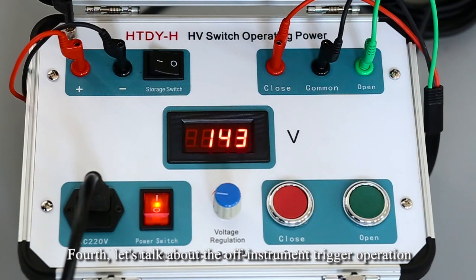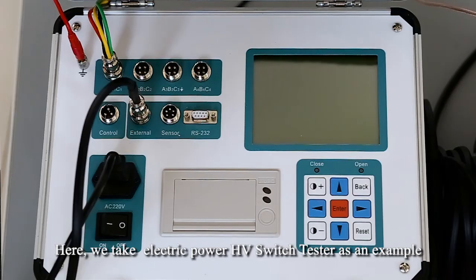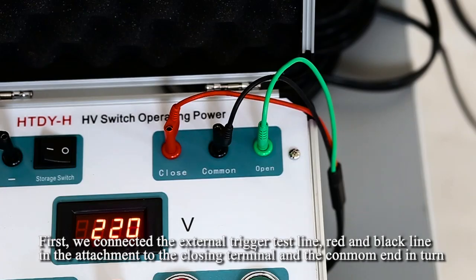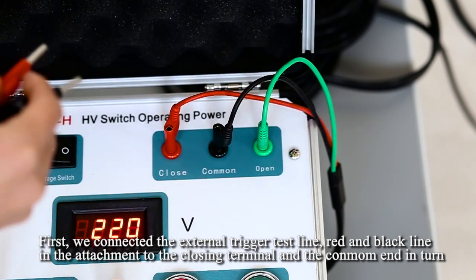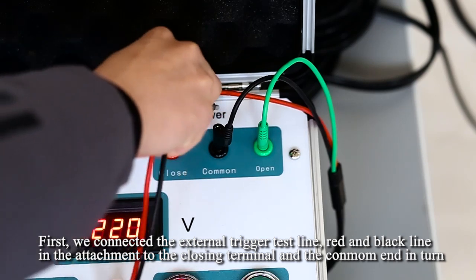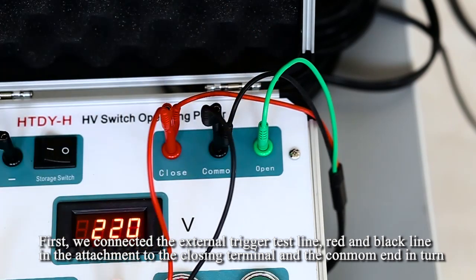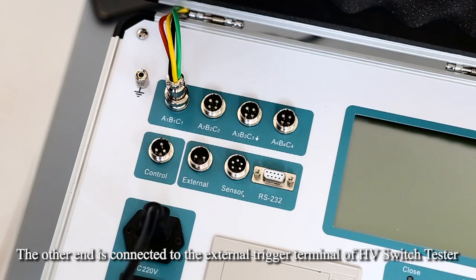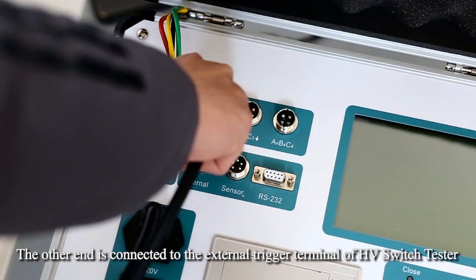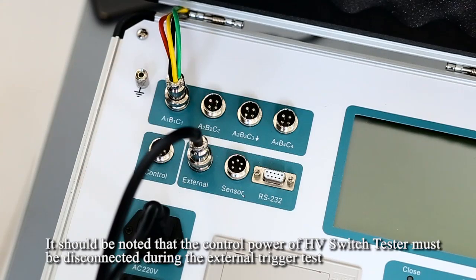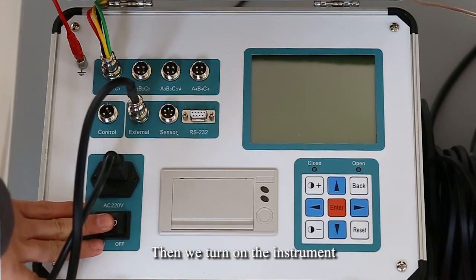Fourth, let's talk about the external trigger operation. Here, we take a high voltage switch tester as an example. First, we connect the external trigger test line, red and black, in the attachment to the closing terminal and the common end in turn. The other end is connected to the external trigger terminal of the high voltage switch tester. It should be noted that the control power of the high voltage switch tester must be disconnected during the external trigger test. Then we turn on the instrument.